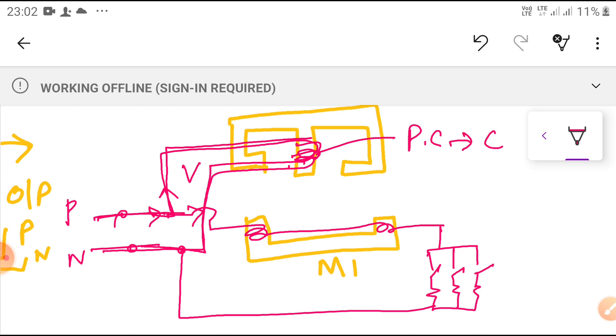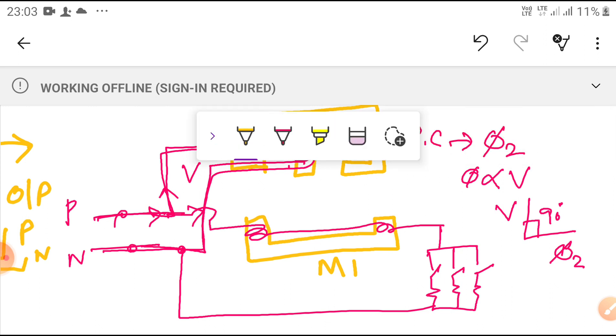The pressure coil produces some flux. The flux is directly proportional to the voltage of this current. The flux always lags the voltage by nearly 90 degrees. The flux produced is phi 2 — there is a 90-degree displacement between the voltage and flux. If it is not exactly 90 degrees, we can forcefully make it so with the help of a shading ring, which we have already seen.